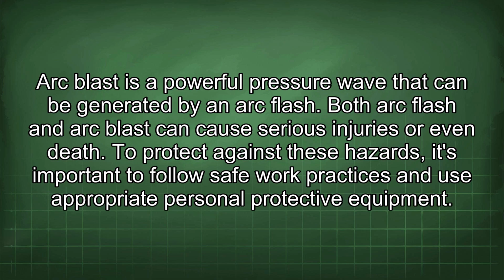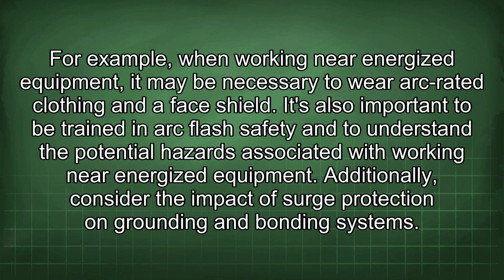To protect against these hazards, it's important to follow safe work practices and use appropriate personal protective equipment. For example, when working near energized equipment, it may be necessary to wear arc-rated clothing and a face shield. It's also important to be trained in arc flash safety and to understand the potential hazards associated with working near energized equipment. Additionally, consider the impact of surge protection on grounding and bonding systems.